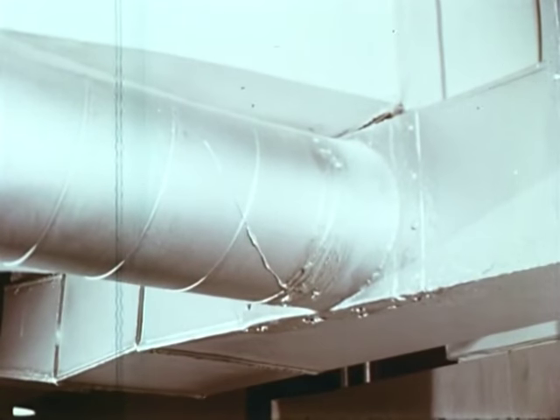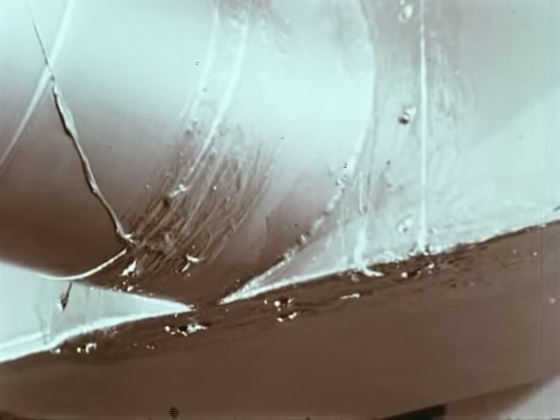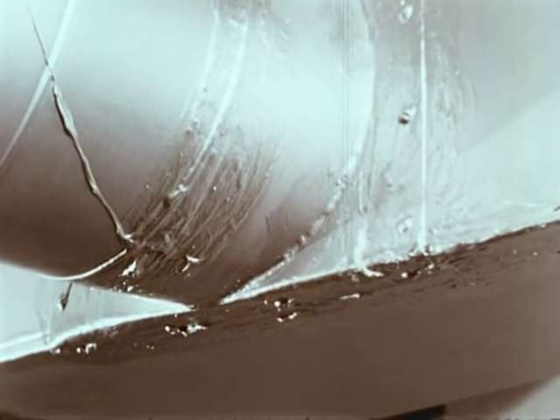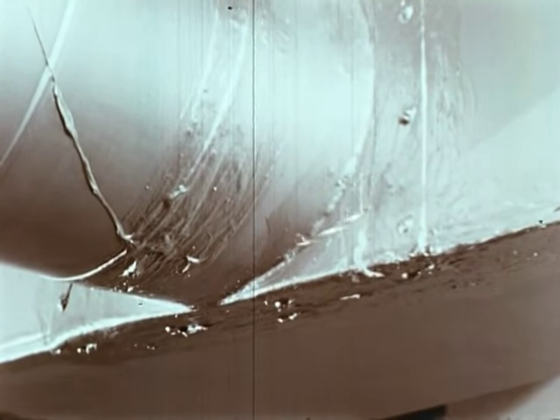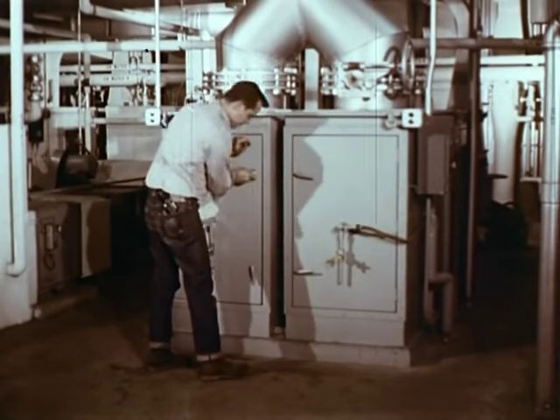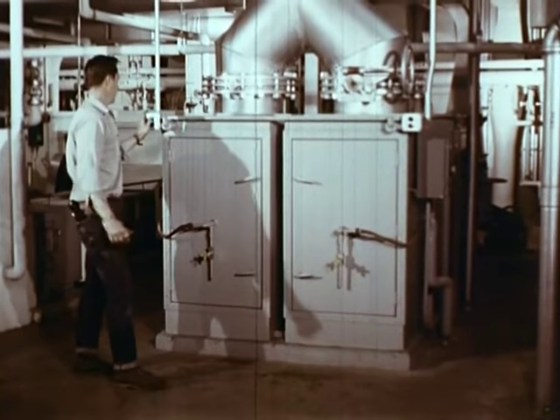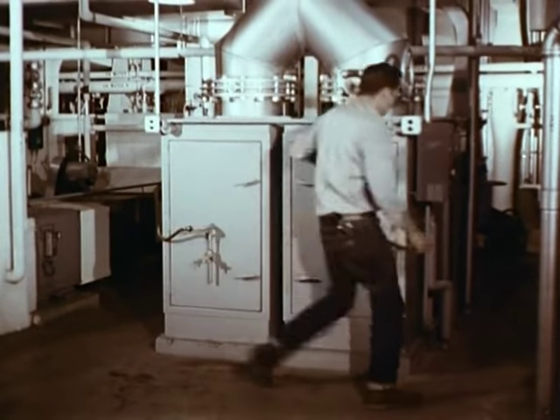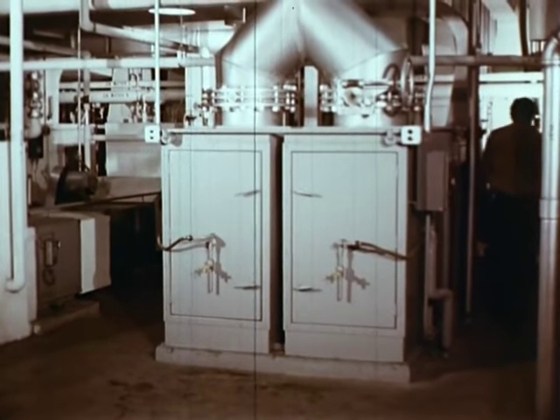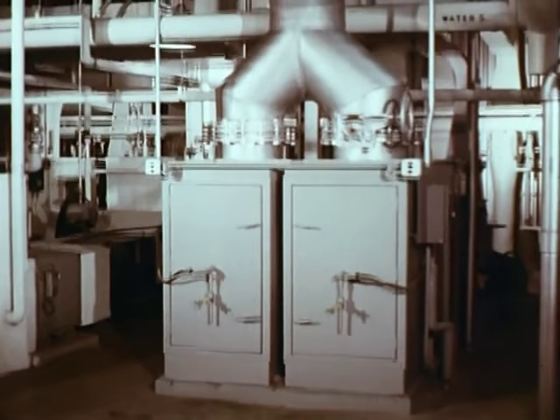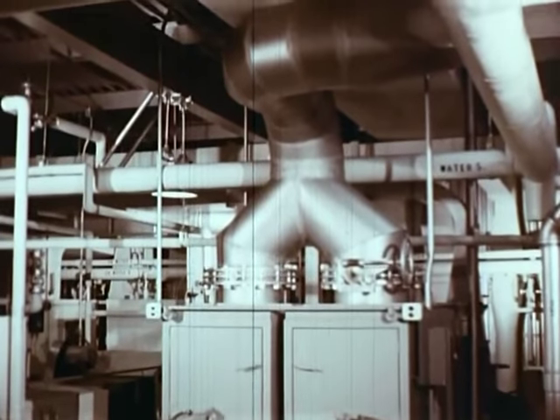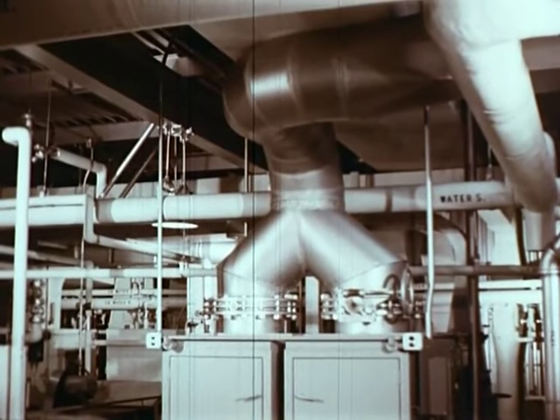Exhaust air ducts coming from the infectious zone must be airtight, however, to assure no leakage of infectious microorganisms before air reaches the exhaust filter plenum. Galvanized ducts with taped epoxy-coated joints have been found satisfactory. The exhaust air plenums in a building are often designed to serve several laboratory rooms of about the same hazard level. They may be equipped either with high-efficiency spun glass mats or with ultra-high-efficiency units for filtering air discharged from the room.